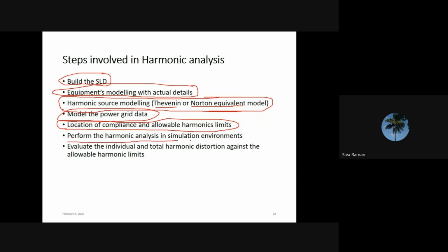Then we have to perform the harmonic analysis for various grid operating environments. For example, the grid voltage depends on various factors, so it can operate from a minimum value to a maximum value. If you have a 10% tolerance, it can go 10% on the positive side and 10% on the negative side. Within that band it can operate, so we have to consider that in the simulation. And importantly, grid strength: whether it is a weak grid or a strong grid, we have to model that.